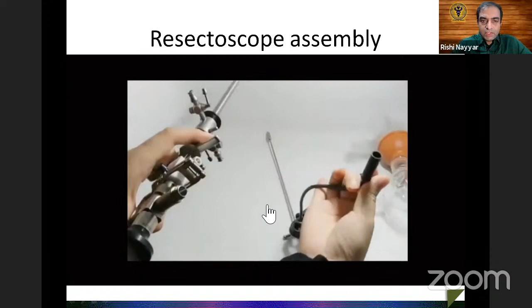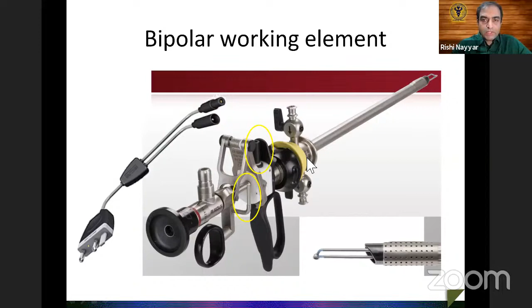The bipolar working element is the same as the monopolar working element, with the only difference that you can see two sides for attachment of this bipolar cord, because both the active electrode and the negative electrode are there in the bipolar system at the tip of the electrode only. So there are two connections here, and this can differentiate between the monopolar and bipolar working element in the simplest manner. The loop itself is made up of tungsten carbide, and for a 26 or 27 Fr resectoscope sheath, the diameter of the loop is 6 mm, which in a way means that the loop by itself will not cut deeper than 3 mm unless it is dug deeper into the tissue.